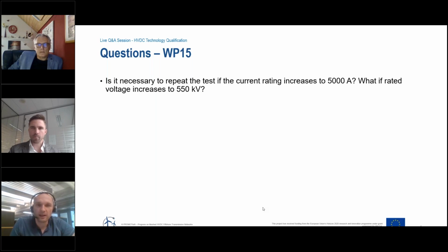increased voltage rating. When we look to an increased current rating, for example, to connect, let's say, two cables in parallel or things like that to increase the current rating, this is not such a big change as long as the temperature difference along the solid insulators stays the same, and we could ensure this by a changed design of the current path, and it can be proven, for example, with the temperature rise test that the temperature difference stays more or less the same, and that would have much less effort than this prototype installation test. So the technical recommendation would be to not repeat the test for an increased current rating.